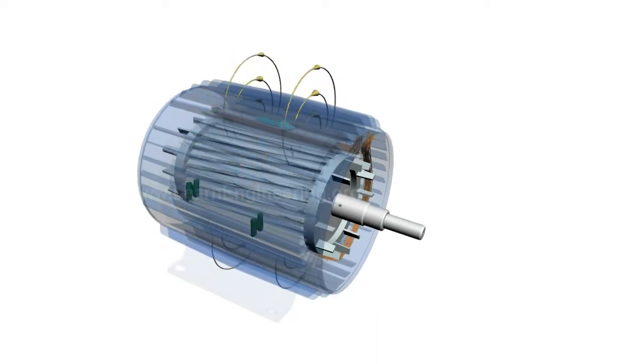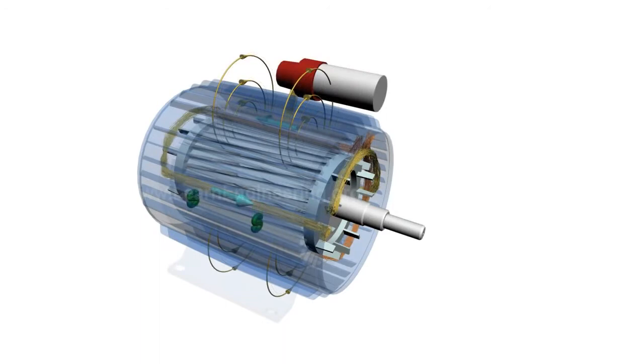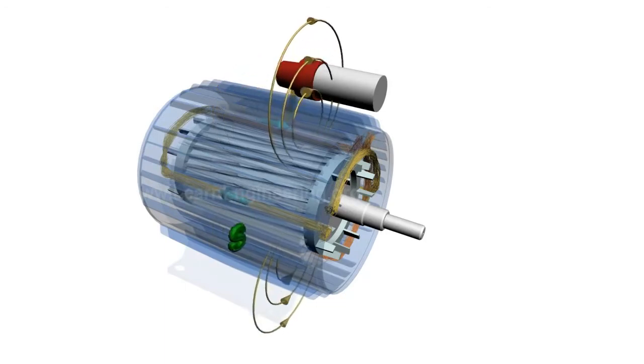The auxiliary winding-capacitor arrangement is used exactly for this purpose. Auxiliary winding also produces two oppositely revolving magnetic fields. One of them will cancel the RMF of main winding and the other will get added up.